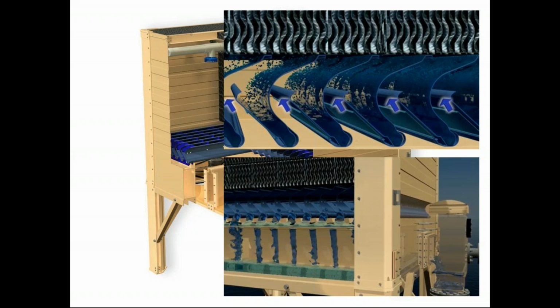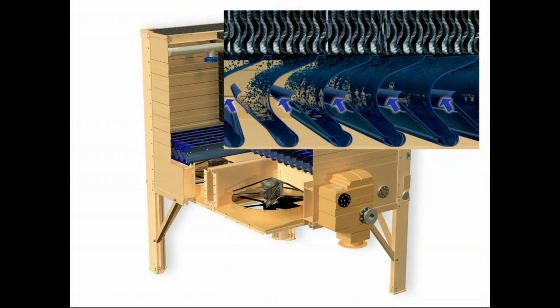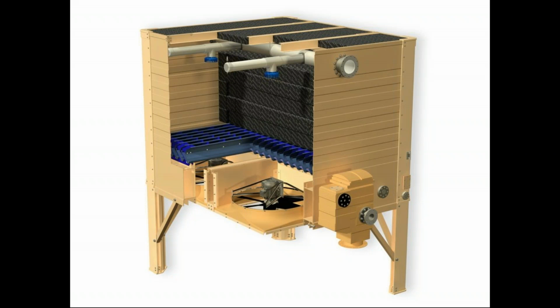So water in this system is always moving very quickly, at a rate of 5 to 7 feet per second. So it's very tough for anything to stay in the system as stagnant water. I'm going to walk back up a little bit. Now let's walk through the air side of it. Air comes in through the fans on the bottom. That water collection system has a damper. So as the fan is running, the air flows through that water collection system, through the fill, up to the top of the TowerTech tower.